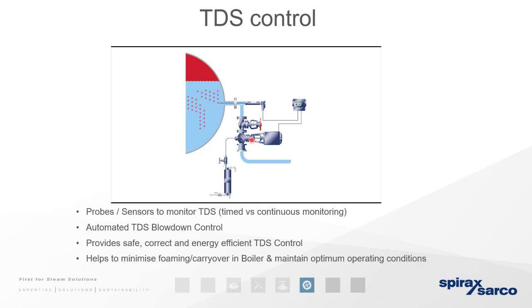So the more TDS you have in your boilers, the more likely you are to have carryover. So that foam is caused by the chemicals that you've dosed into your boilers, by the collection of TDS as well. So it is more likely to foam inside your boilers if the TDS is not correctly monitored.